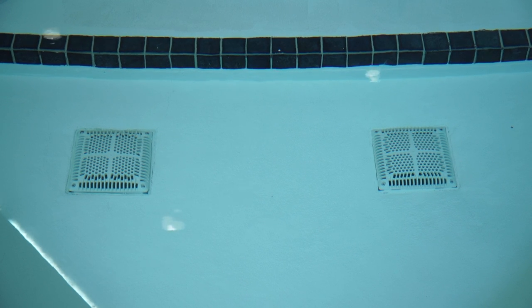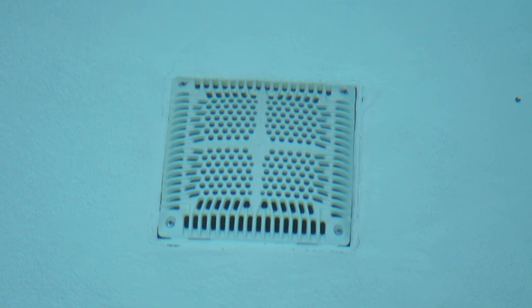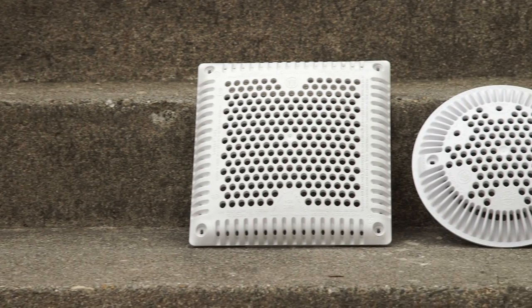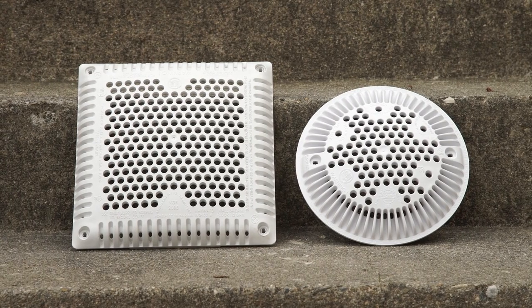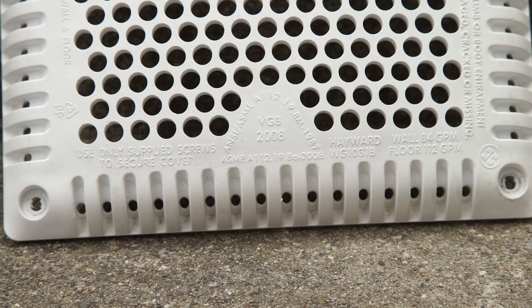All suction outlets must be appropriately covered with a Virginia Graeme Baker compliant outlet cover, also referred to as VGB. Drain covers have undergone strict testing to meet VGB requirements, and the compliance mark should be on the cover or matched with a make and model number to the manufacturer's or engineer's paperwork.